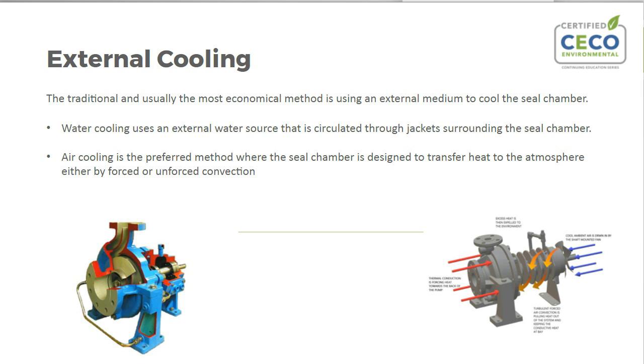Oftentimes you were pumping anywhere from a half gallon to 4 gallons a minute through the pump, depending upon the temperature that you wanted to bring the seal down to. With that in mind, it was incredibly wasteful. It was expensive. Water is a precious resource, as most of us know. Depending upon where you are in the world, it may not be available, such as desert applications. Now we still do use water-cooled pumps today, but they've been taken over by air cooling for the most part in high-temperature applications.